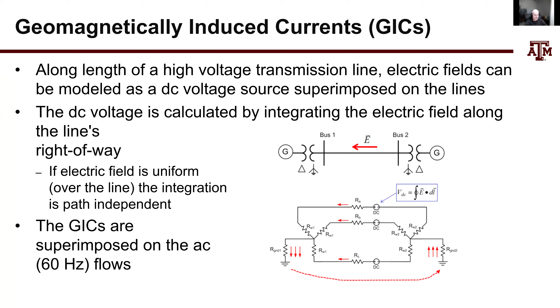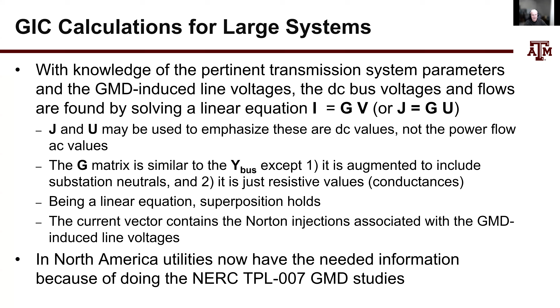Once you get these, you can take a model of the power grid and calculate how the GICs flow everywhere in the grid. This is something most utilities are getting familiar with because it's done for GMD analysis, the same sort of thing we do for representing E3 impact on the grid.